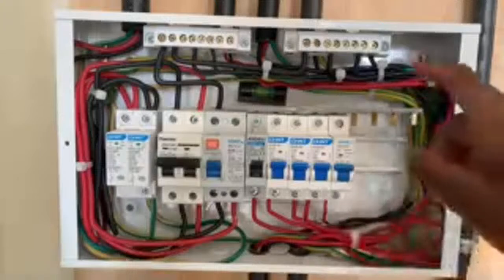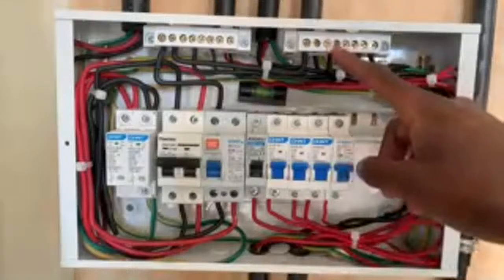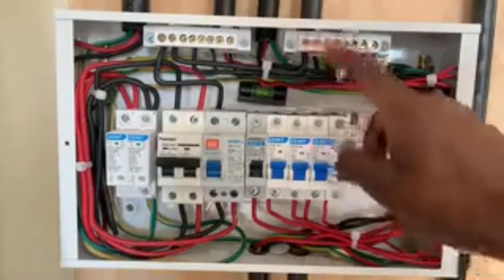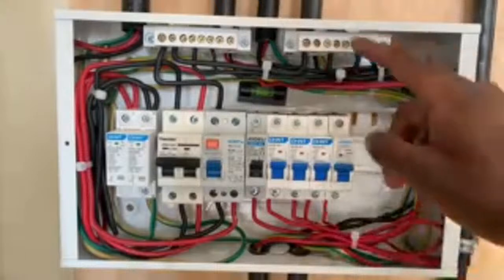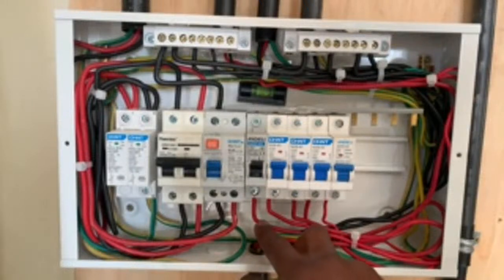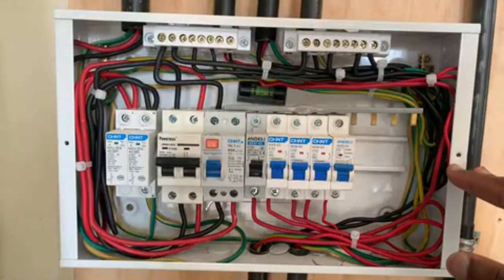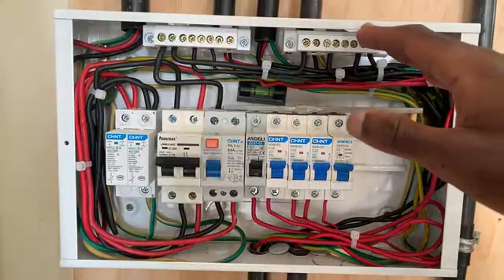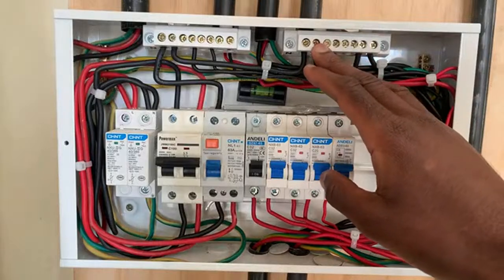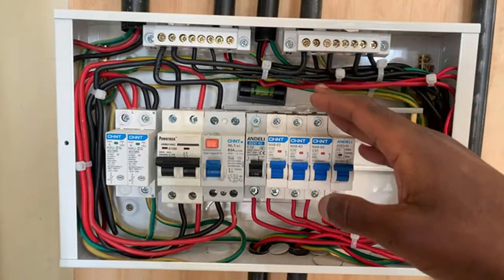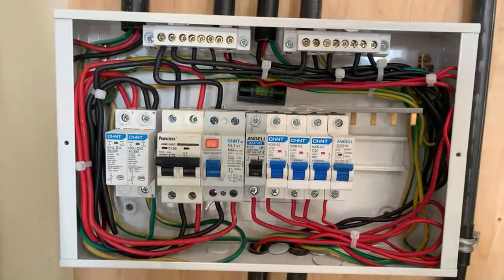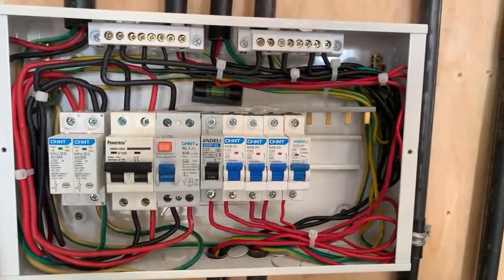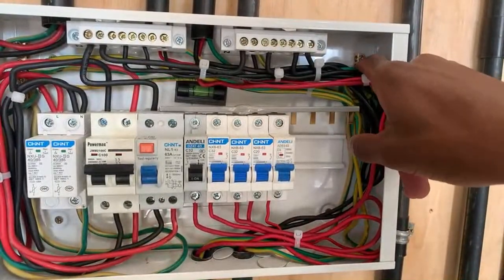Sorry about that. Time for me to take some water. So current will have to flow back to the source here, which in our case is this, and it will have to come back to this bar here. So for it to make a complete circuit, it comes out from the MCB through the 4.0 square cable, goes all the way to the connection at the cooker, and then it has to get back to the neutral bars. So when it gets back to the neutral, it means that is a complete circuit. But again, you may ask, John, why would you then have the same size when it comes to the earth connection?